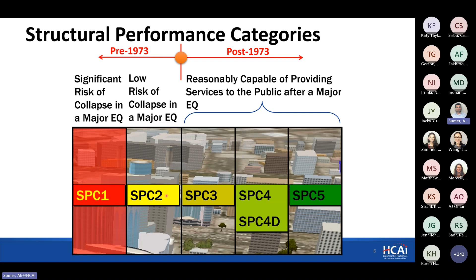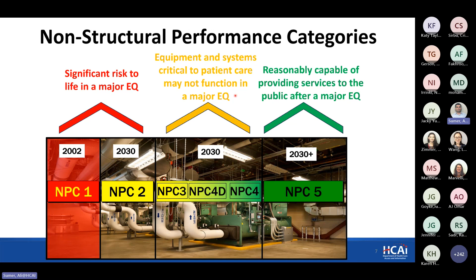NPC, what those mean, again, NPC 1 is the worst, NPC 5 is the best. NPC 1 and 2 really pose significant risk to life in a major earthquake. NPC 5, on the other hand, is reasonably capable of providing services to the public after a major earthquake. Now, if we look at in between, 3, 4D, and 4, those do require some anchorage to equipment and distribution systems, but they are not, for example, addressing water, wastewater, emergency fuel. So we categorize these ratings as equipment and systems critical to patient care that may not function in a major earthquake.